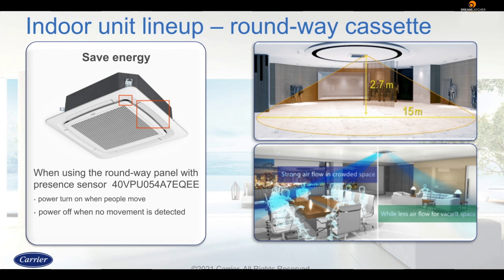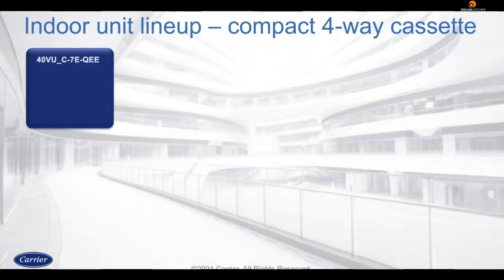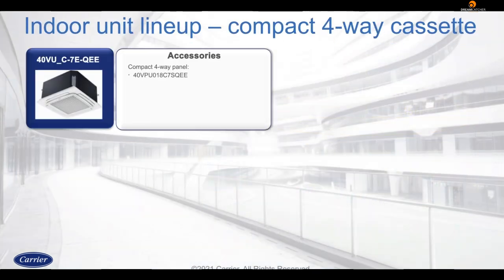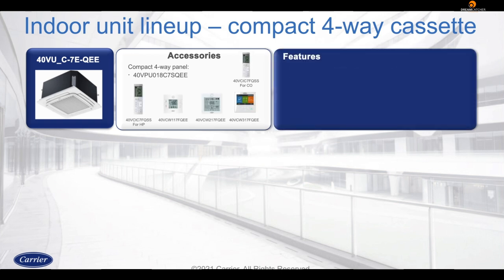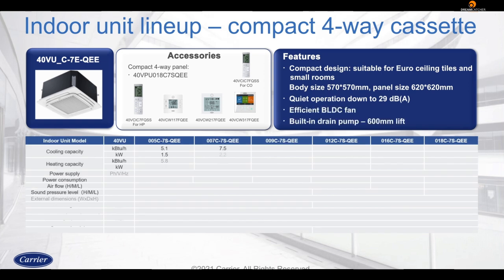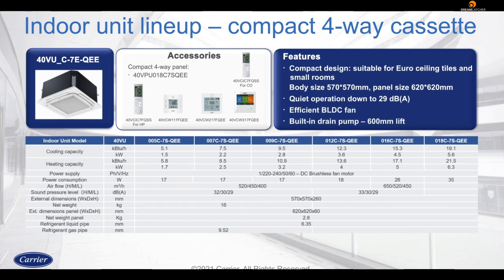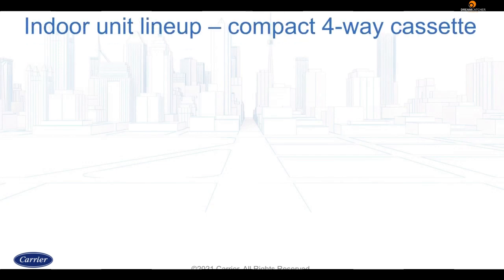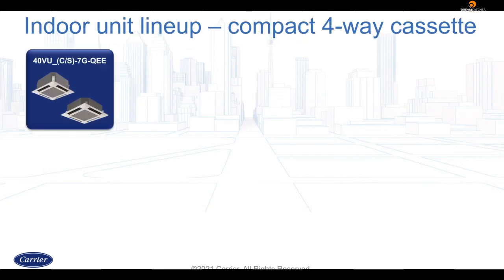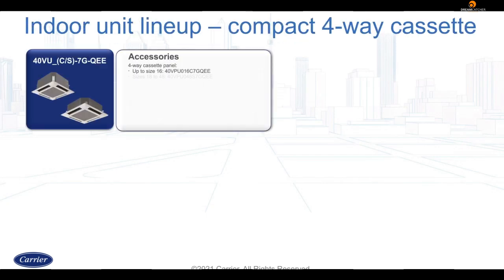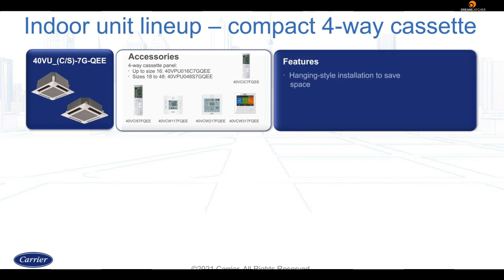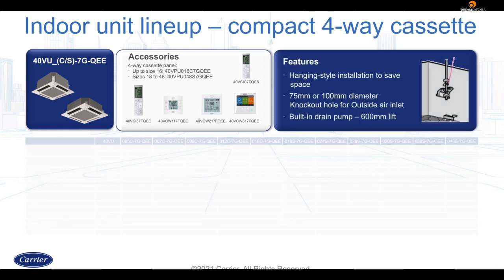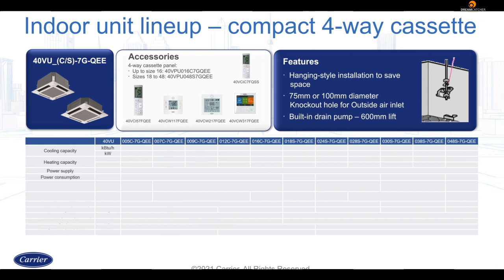The compact 4-way cassette offers a compact design that is suitable for 600 by 600 ceiling tiles and small rooms. Quiet operation down to 29 decibels thanks to the efficient BLDC fan is one of its hallmarks. The standard 4-way cassette comes in a cooling range of 5.1 kBTU per hour to 47.8 kBTU per hour. It also comes with a hanging installation that helps save space and has an inbuilt 600 mm lift drain pump.